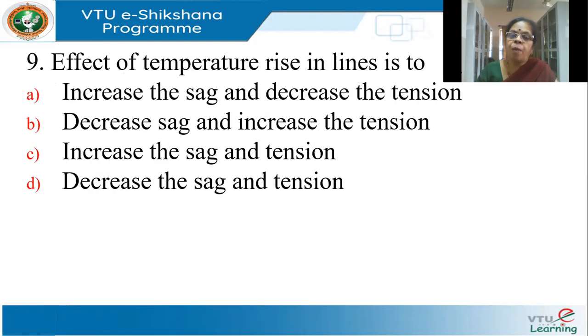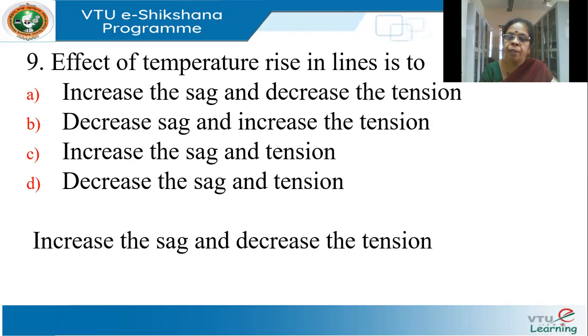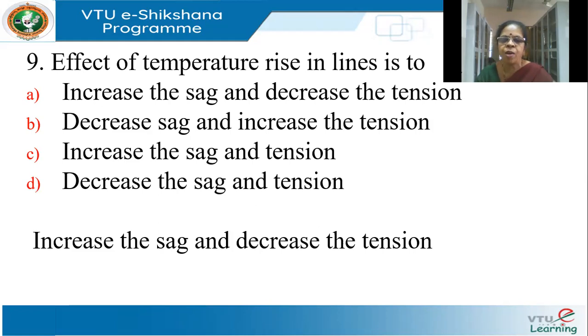What is the effect of temperature rise on lines? When temperature increases, sag will increase and tension will decrease. Sag and tension are inversely proportional: S = WL² / 8T. So both cannot increase or decrease simultaneously — options C and D are ruled out. Temperature heats up the conductor, so it will bend more and sag increases. The correct answer is: increase the sag and decrease the tension.